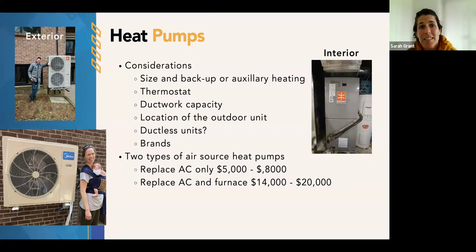Ductwork capacity is also important to keep in mind - work with an HVAC contractor who understands how to properly size the heat pump, not just for the heating requirement, but because the air from a heat pump isn't as hot as from a gas appliance, so it needs to push more air. If your ductwork is a bit small, that may be why a contractor recommends a slightly smaller heat pump than you'd like. Getting that tested and checked is important.